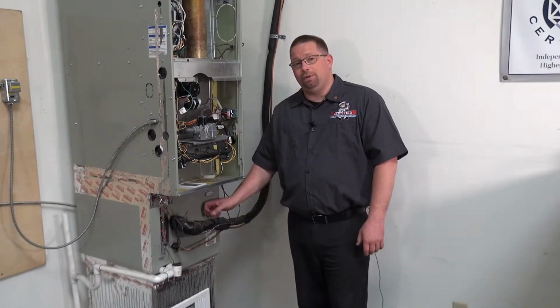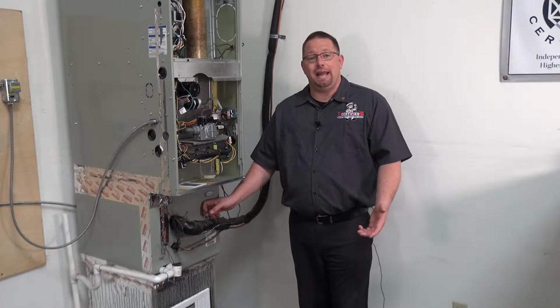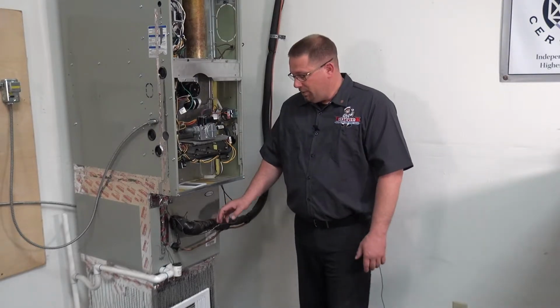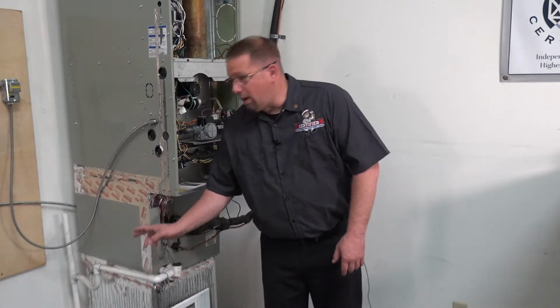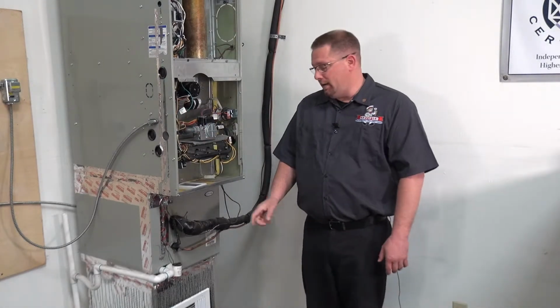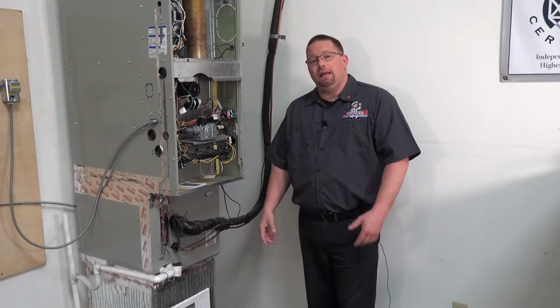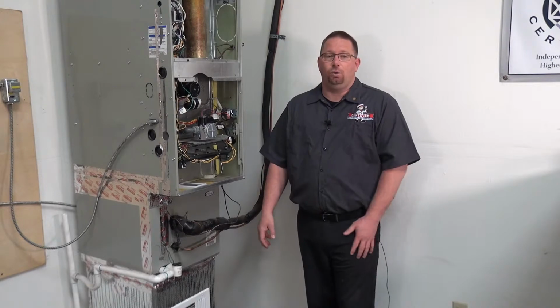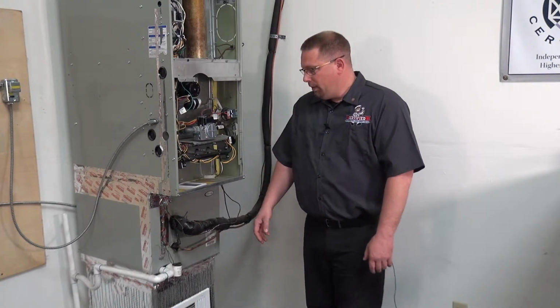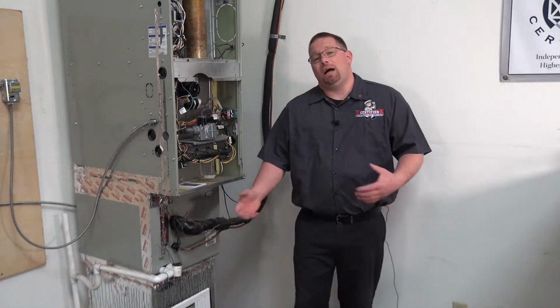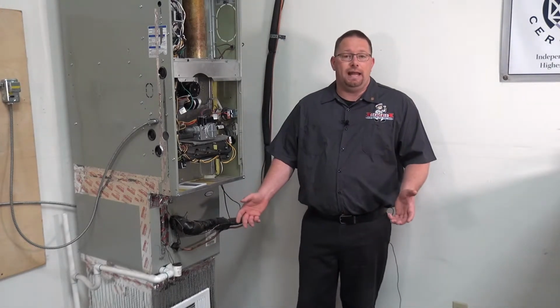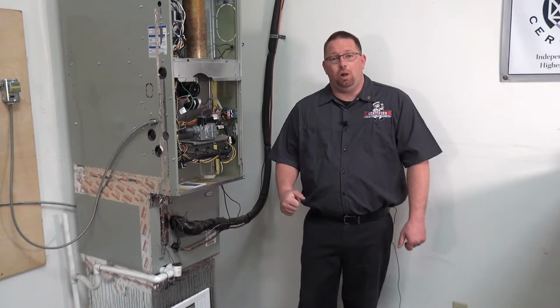The water this thing produces could be a couple gallons a day, depending on outdoor temperatures. We want to make sure this drain line properly allows the water to go outside, not down inside a supply plenum and out into your ductwork, because water in cold, dark places is not a good idea. We also want to make sure there's some kind of emergency overflow device that stops the unit from flooding ductwork or flooding the house when the drain system gets clogged up.